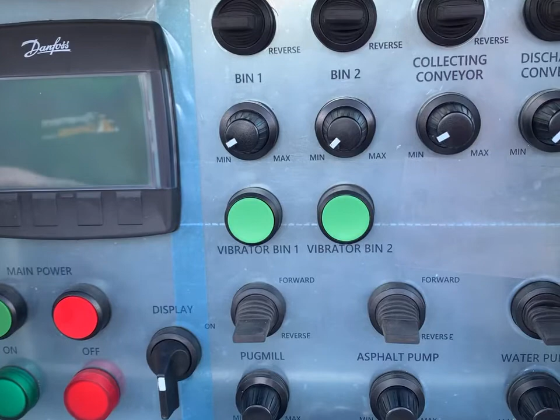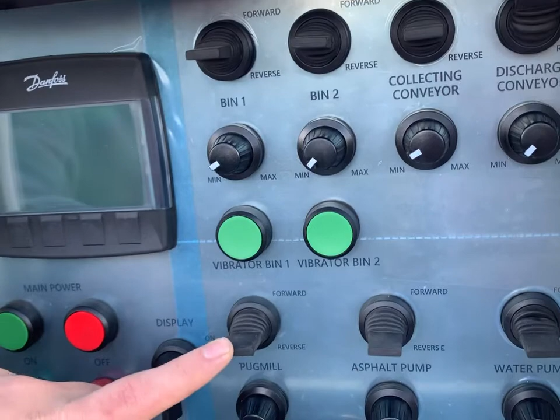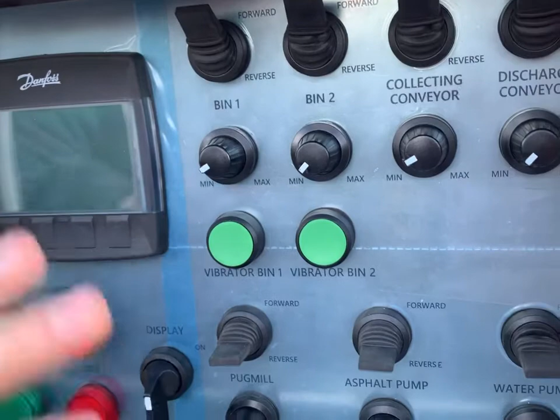You've got your discharge conveyor at the end here, and all of these have to be satisfied in a row. When we flip our discharge conveyor up, that's the first thing to start running, and then we work our way down the machine to the pug mill, which has to be on next to satisfy the switch for the collecting conveyor. Once the collecting conveyor is on, we can turn on the switch for bin 2 and then bin 1. If at any time one of these gets shut off and interrupts the system, all of the belts will stop.